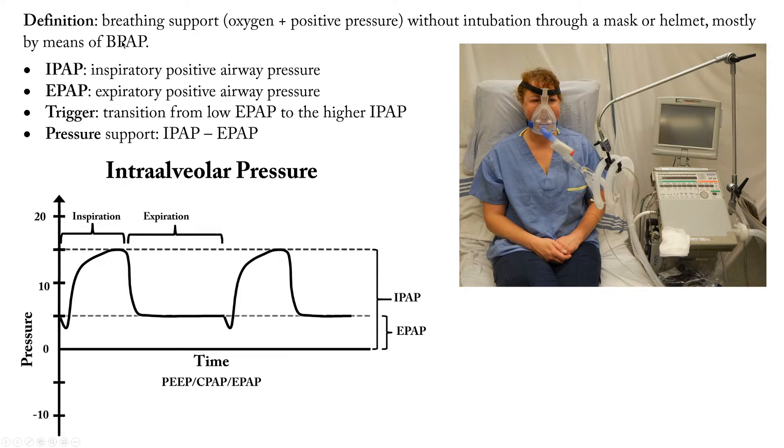The means through which we give non-invasive ventilation is by BiPAP, mostly. First, we need to know these definitions: IPAP is the inspiratory positive airway pressure, and EPAP is the expiratory positive pressure. The IPAP is higher, the EPAP is lower. The trigger is the transition from the low EPAP to the higher IPAP, and the pressure support given to this patient is the difference between the inspiratory positive airway pressure and the expiratory positive pressure.